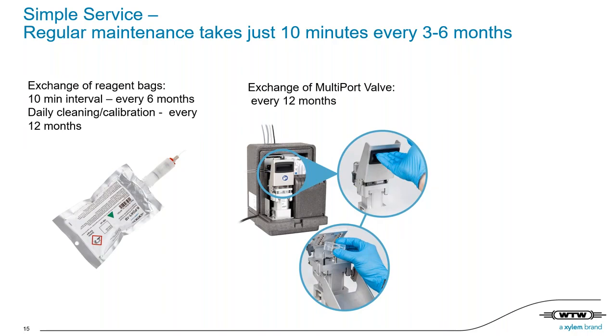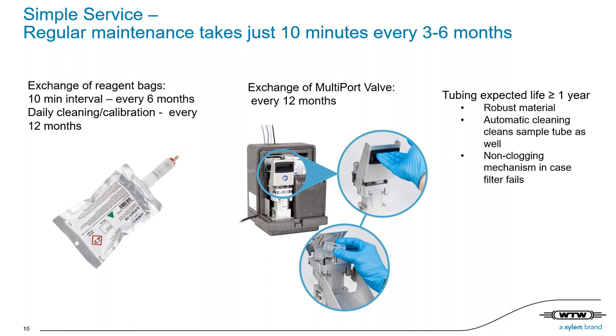So what's left? We also improved the tubing to minimize replacement requirements. Most of the tubing is only air or solution contacted, and also the sewage pump inside, and thus the replacement is not expected. Sample contacted tubings should last more than 1 year. We improved the material and added automatic cleaning to the tube from the overflow vessel to the multiport valve and the photometer sample tube, so that maximum durability and lifetime is given.